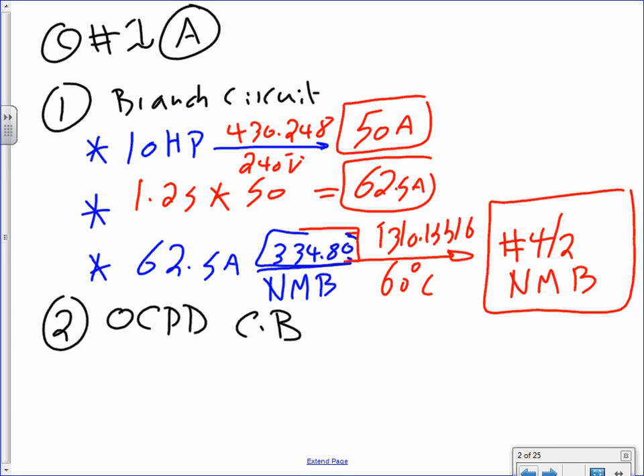A 4-2 NM cable. Number 4/2. Two conductor number 4. Why two conductors? We don't need a neutral. So that's the size of the conductor that you need.